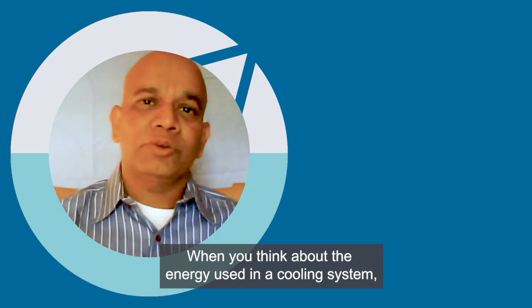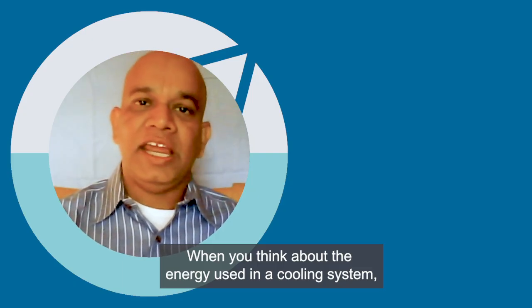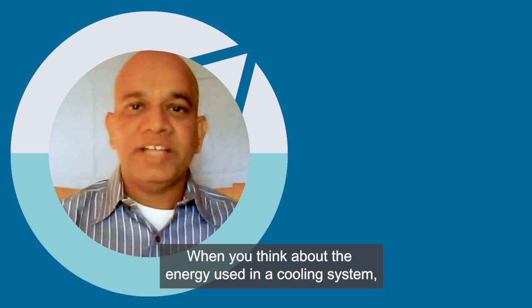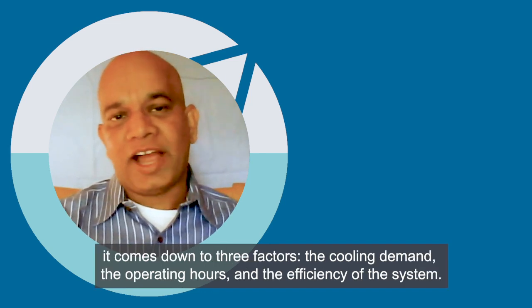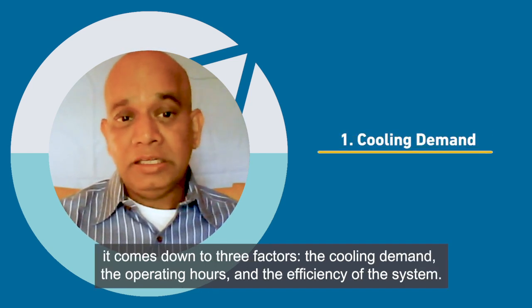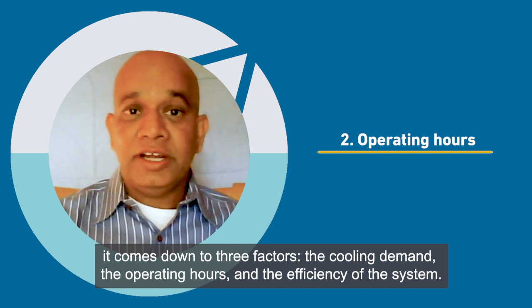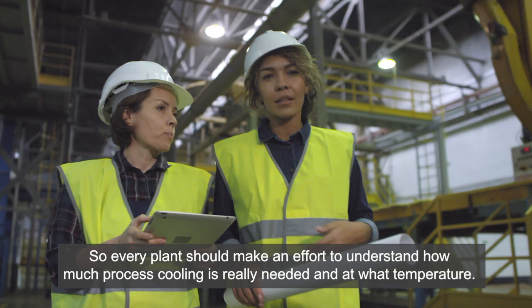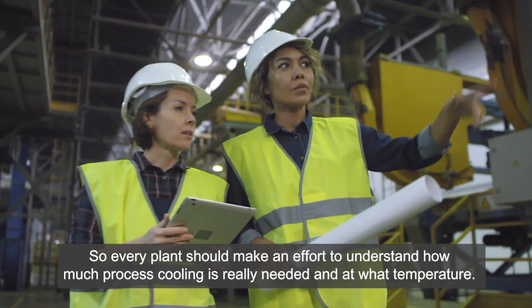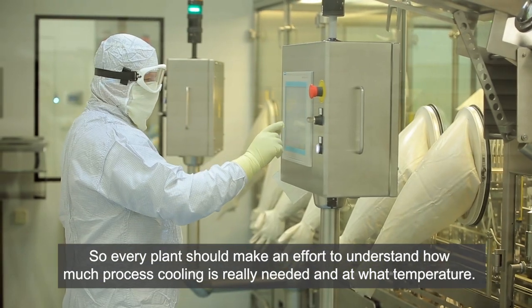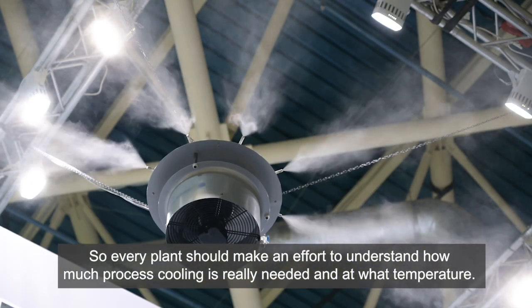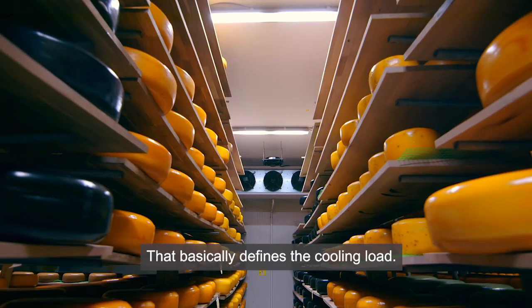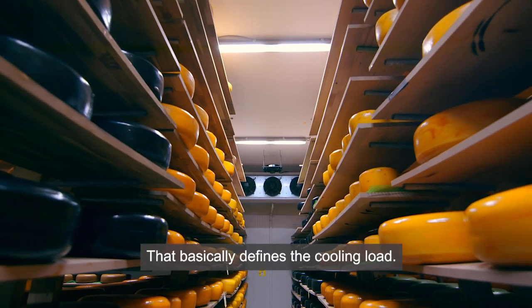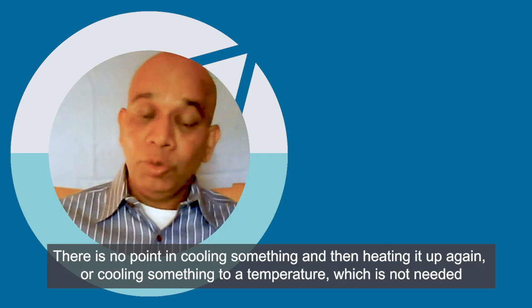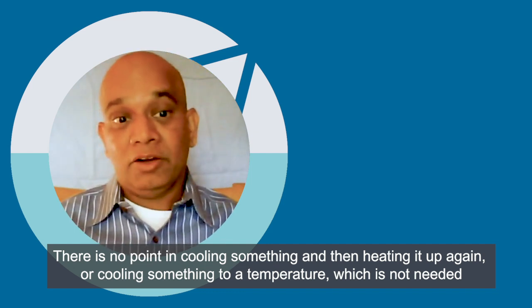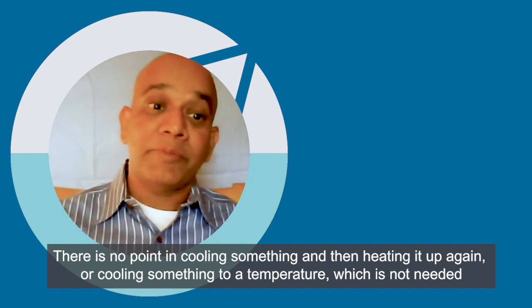When you think about the energy used in a cooling system, it comes down to three factors: the cooling demand, the operating hours, and the efficiency of the system. Every plant should make an effort to understand how much process cooling is really needed and at what temperature. That basically defines the cooling load. There is no point in cooling something and then heating it up again, or cooling something to a temperature which is not needed.